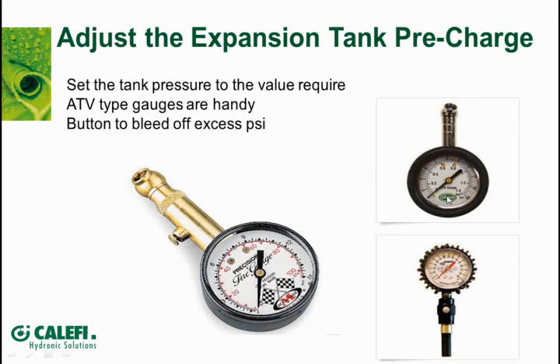When I go to replace this, I found a little bit nicer one online. This one goes up to a little higher pressure, up to 20 psi, and it looks like it's got a little rubber thing around it, because mine, the glass is already broken on. It's getting pretty beat up. But you can find these at your local auto supply places. Another thing I like about this one and also this one, you'll notice it's got a little push valve on the side of it. So you put this on your expansion tank, and let's say it goes up to 15, and you're going to fill your system to 10 or 12 pounds pressure. All you have to do is push that with your thumb, and it'll let the pressure off.